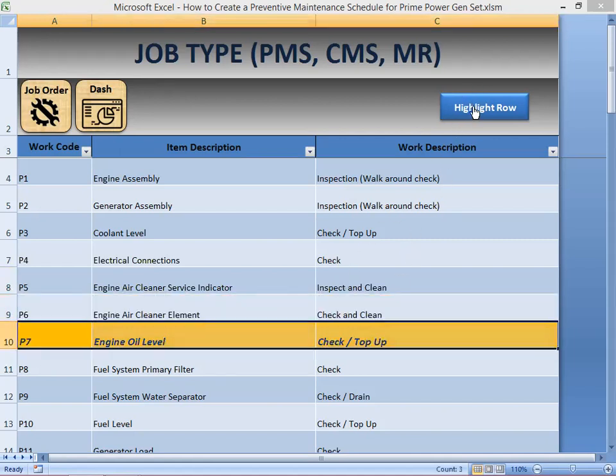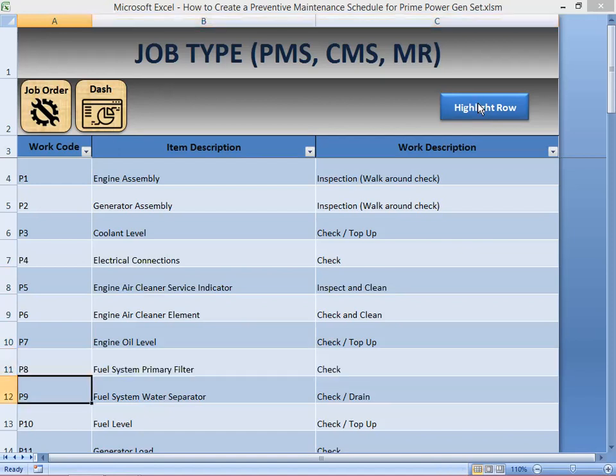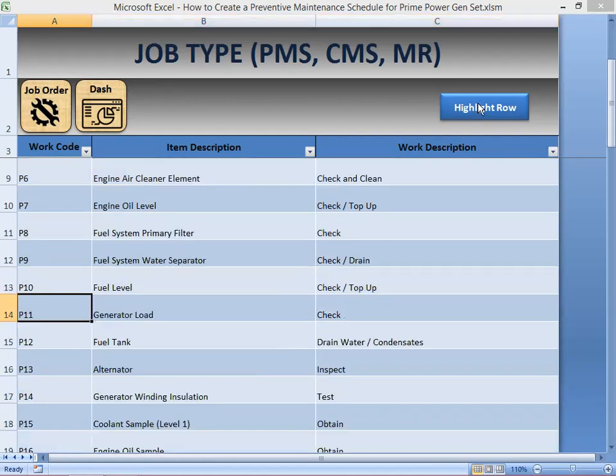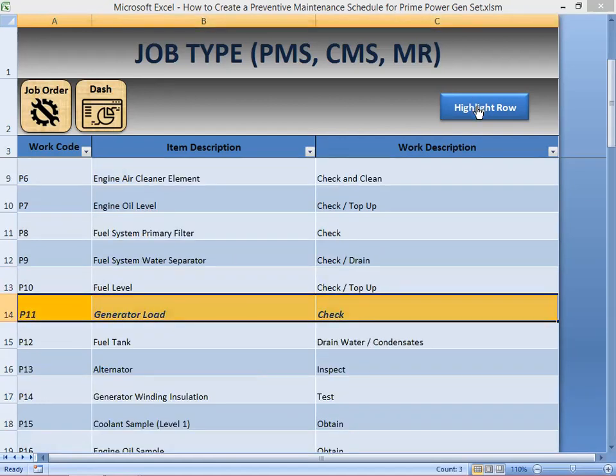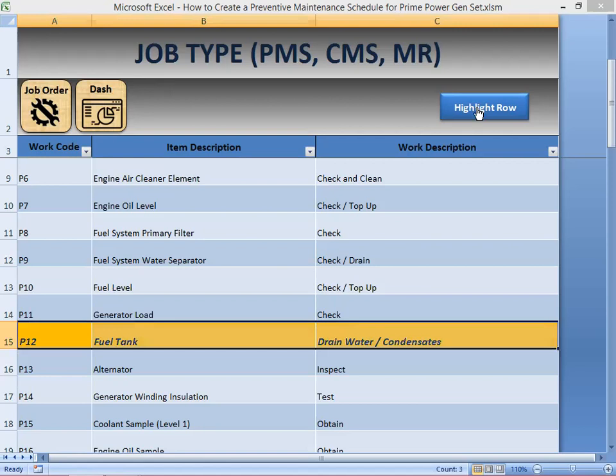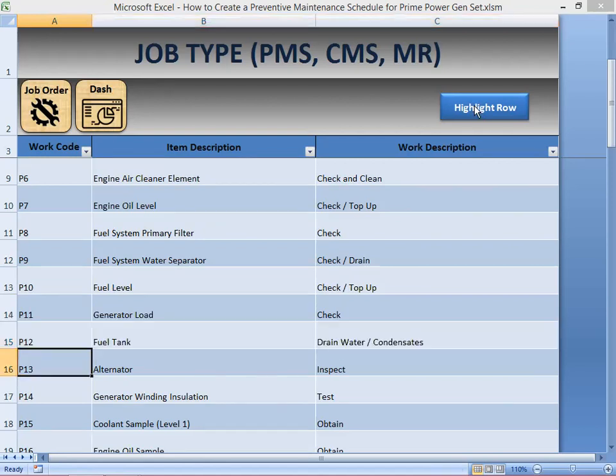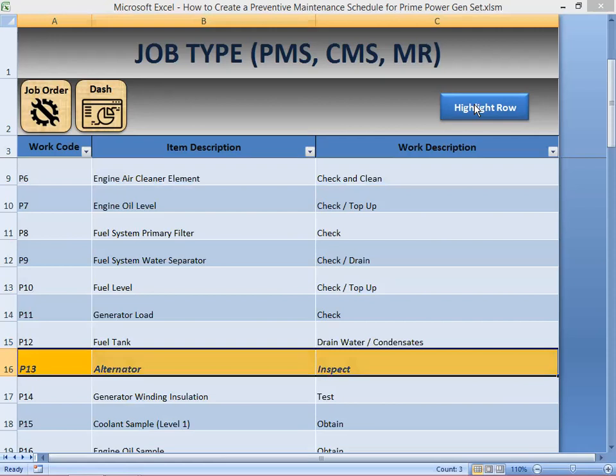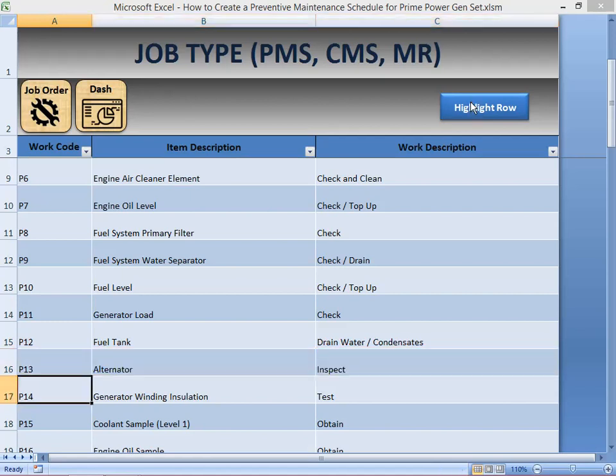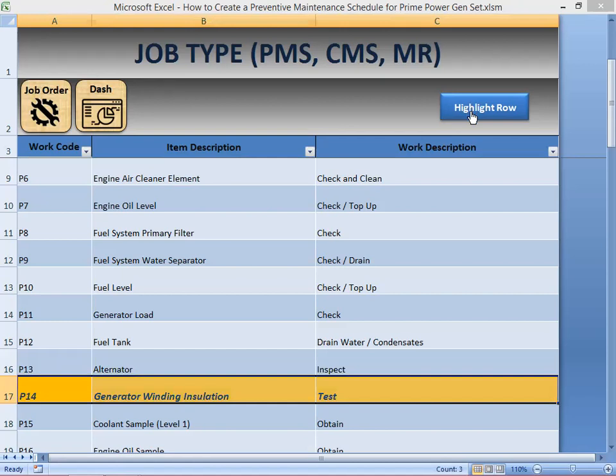Then next one will be engine oil level, check and top up. Fuel system primary filter, check. Fuel system water separator, check. Fuel level, check and top up. Generator load, check. Fuel tank, drain water condensates. Alternator, inspect. This is the charging system of the engine. Okay. The generator winding insulation, test it.